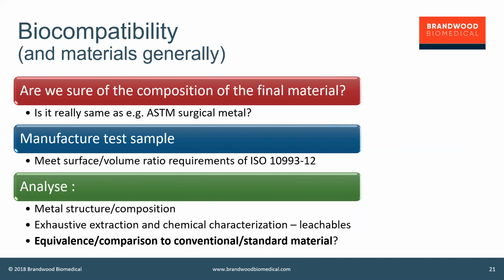An exhaustive extraction is when you take the sample and you place it into a solvent for a defined time period, usually at an elevated temperature. Typically for implants, you'll be looking at 70 degrees for 24 or 70, 48 or 72 hours, but an accelerated temperature for a reasonable length of time.